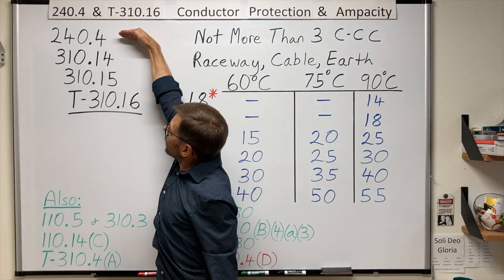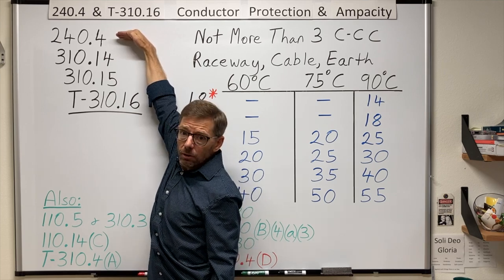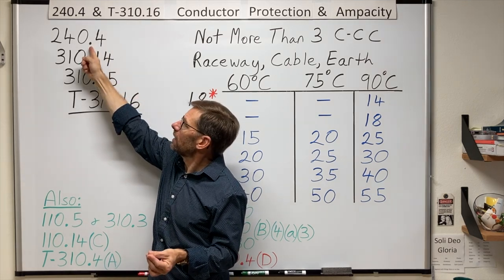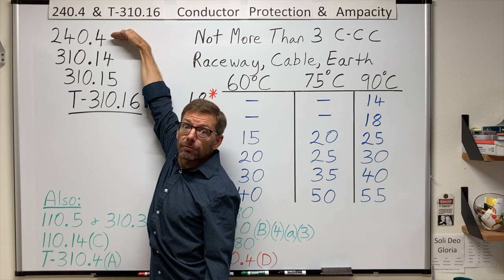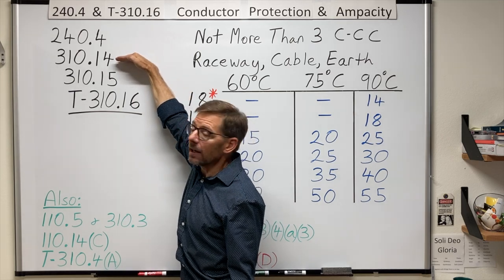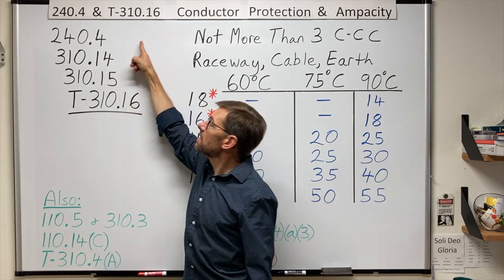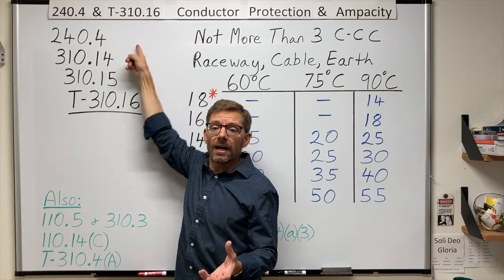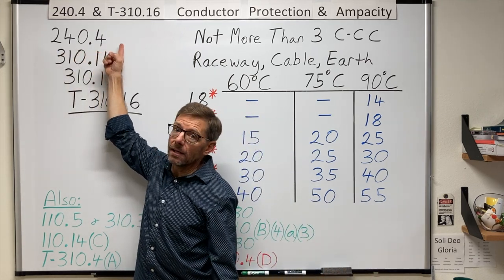Well, let's jump in. 240.4, protection of conductors. It says, general, it says that conductors, other than, and then it lists a couple types that are talked about in .5, but generally speaking, conductors shall be protected from overcurrent based on their ampacities found in 310.14. But before I go here, I've got to finish my sentence. It says, use these ampacities unless otherwise permitted or required in 240.4 A through G.